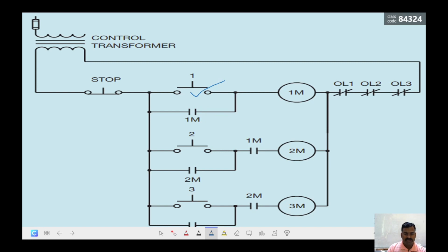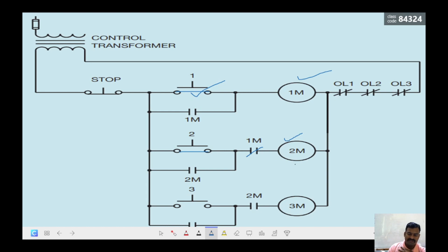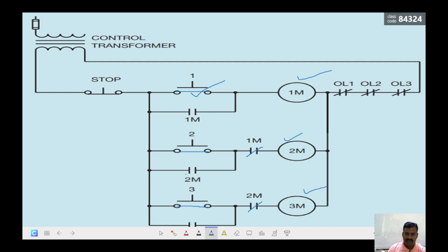In this alternative arrangement, switch number one is placed here; when it is operated, coil number one gets energized, and when coil one is energized it makes this path closed so that the second coil is ready to receive signal from switch number two. When switch two is closed, the second contactor energizes and the motor runs. When that coil is energized it closes the path so switch three can transfer energy to the third relay coil or contactor. In this way we can also organize this control circuit. Let us see the simulation.